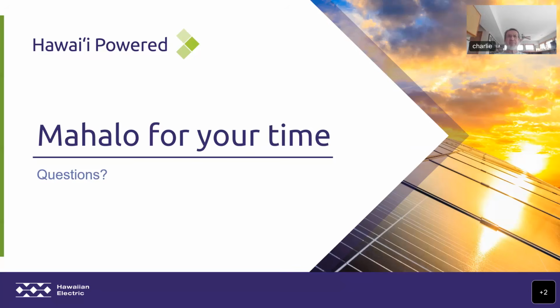Okay. How do you plan to overcome the gaps in traveling wave protection if replacing line differential relays with traveling wave relays? So, traveling wave relays, again, the speed is what we'd be looking for. We can't make critical clearing times with current differential and the current circuit breakers. So, traveling wave will offer sub-cycle detection performance. But if you're still operating a 3-cycle breaker, that may not get you much. So a combination of traveling wave and faster circuit breakers is kind of what we're seeing for the future. Maybe it just depends on the critical clearing times that we need to meet with the protection systems.